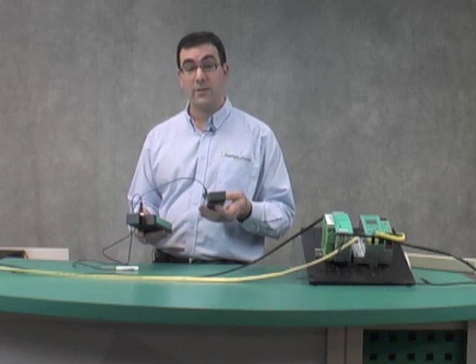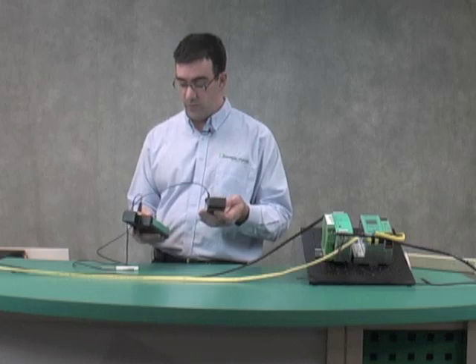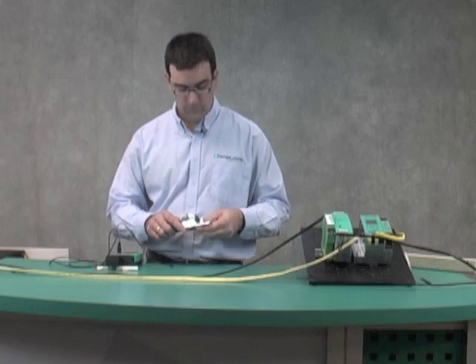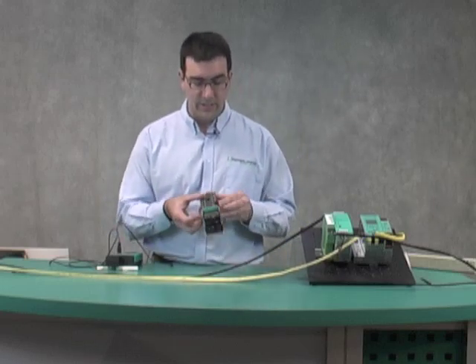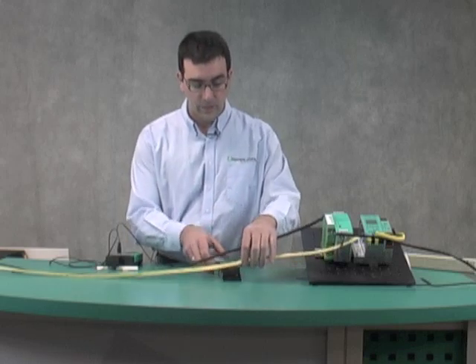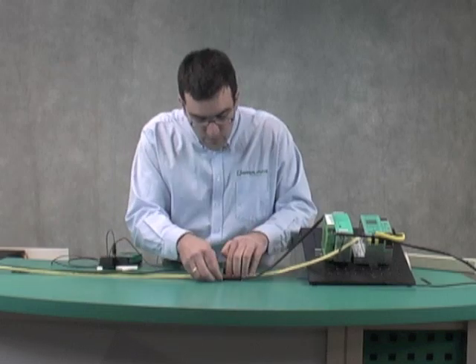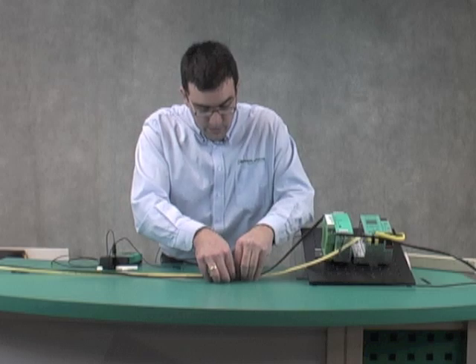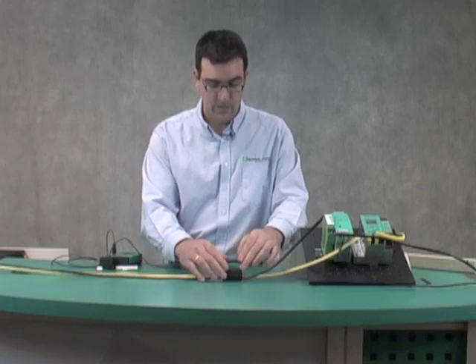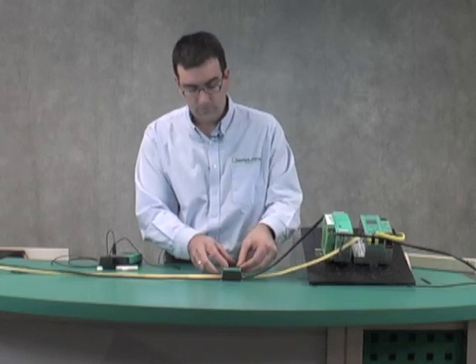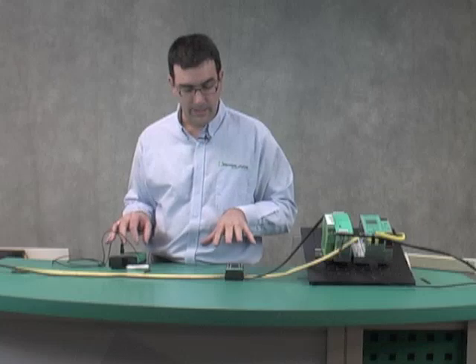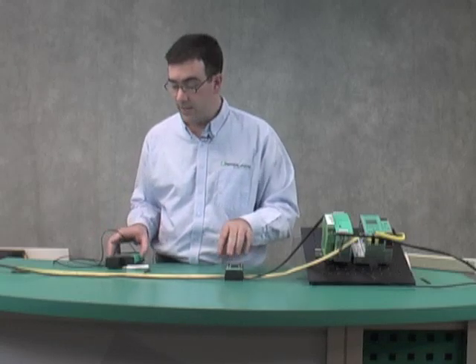So I'm going to make this 1A. The address is going to be 1A through 31A, 1B through 31B. So I'm going to program that, read it back, double check. All right, slide this back. This is called the G12 tool-less design. You're going to slide the top back, put the flat cable in both trays, lay the cable in. Make sure it's seated properly. Slide the top of the module back. Press it down. Pretty simple to do. You can see your ASI flat cable. You can see it's nice and parallel. And so I got one module on here, address 1A. Let me put another one on.